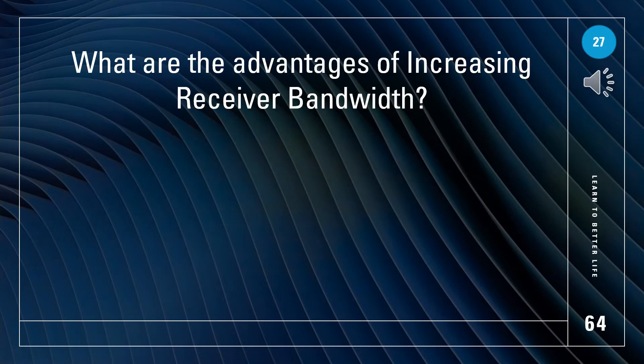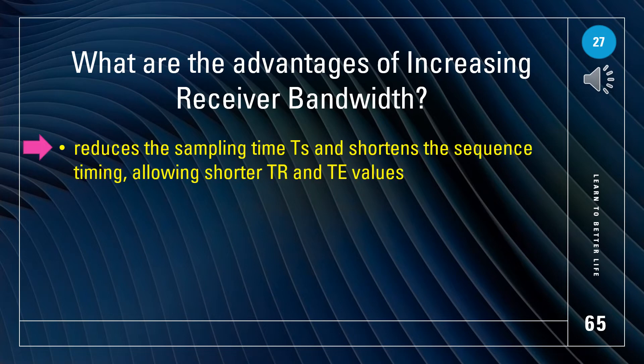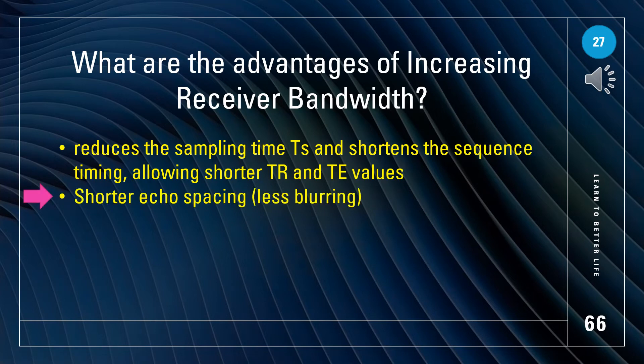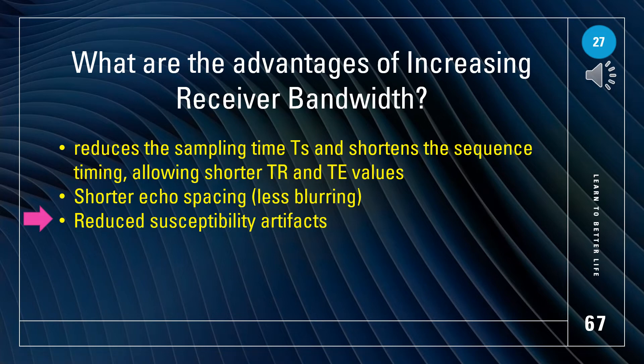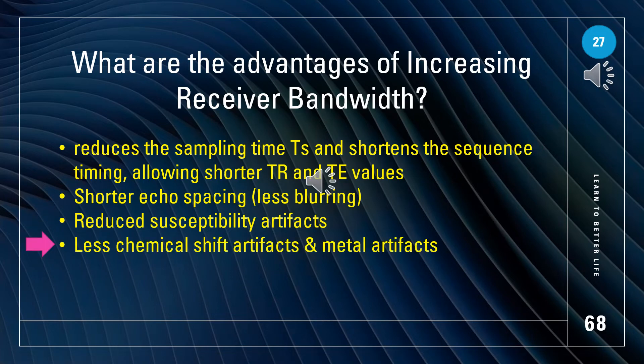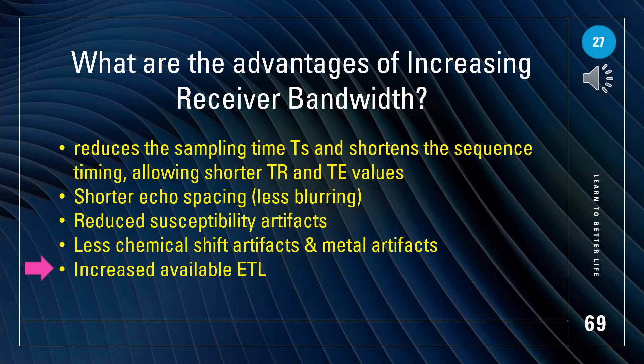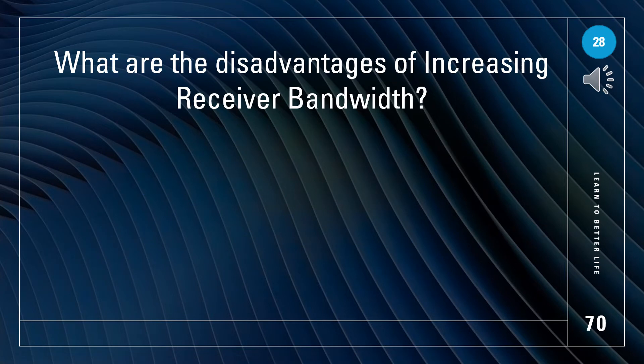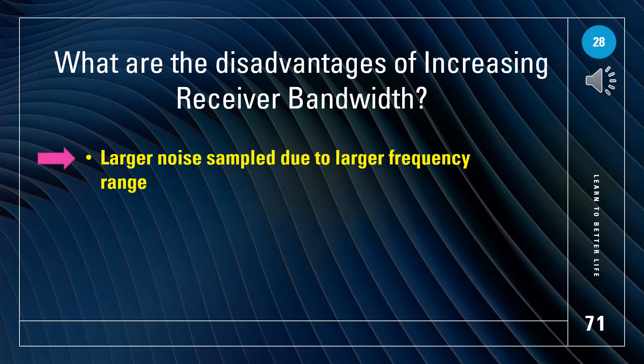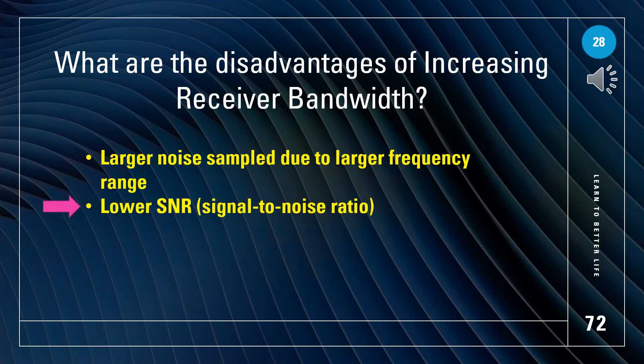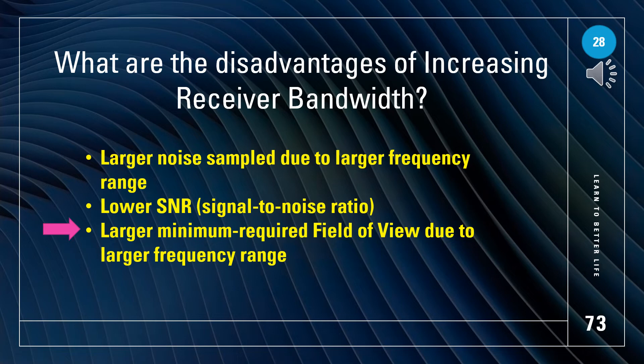Advantages of increasing receiver bandwidth: high receiver bandwidth reduces sampling time T and shortens sequence timing, allowing shorter TR and TE values; shortens echo spacing resulting in less blurring; reduces susceptibility artifacts; reduces chemical shift and metal artifacts; and increases the available ETL. Disadvantages of wide receiver bandwidth: larger noise sample due to larger frequency range, lower SNR, and requires a larger minimum field of view due to the larger frequency range.